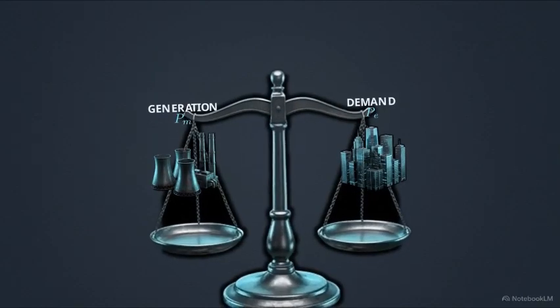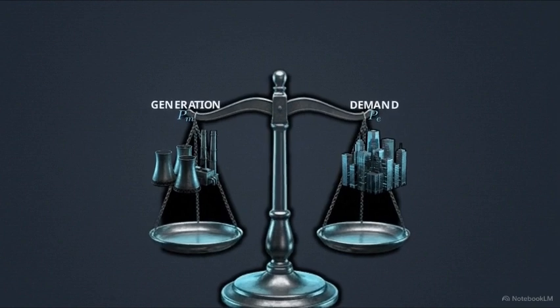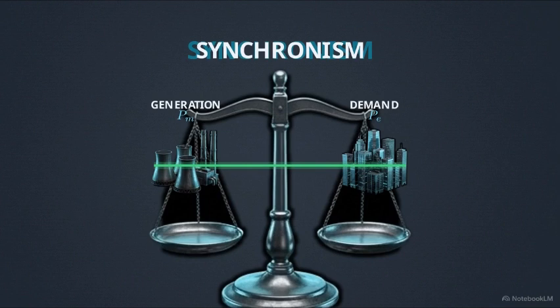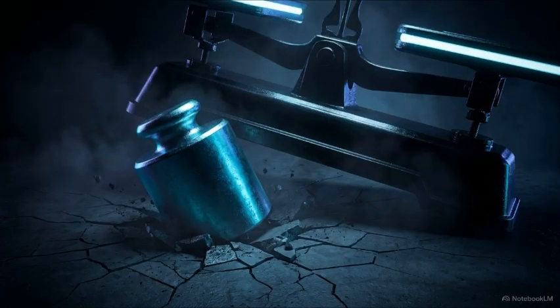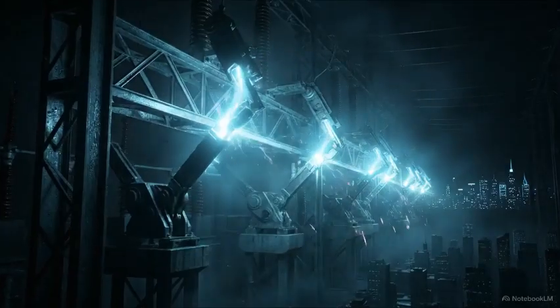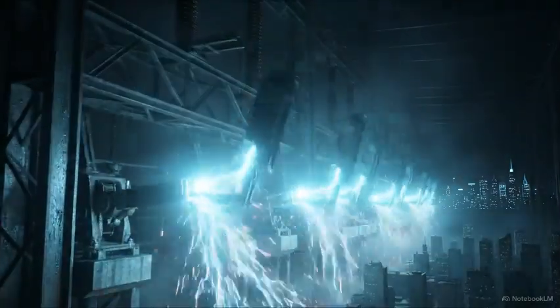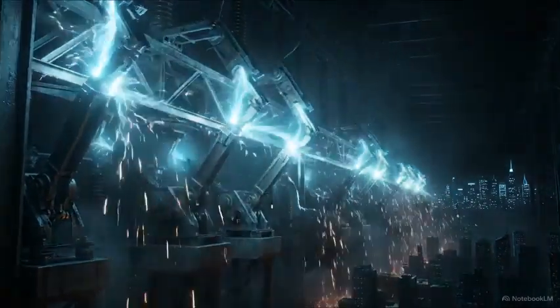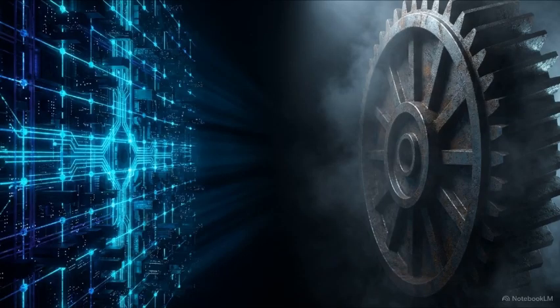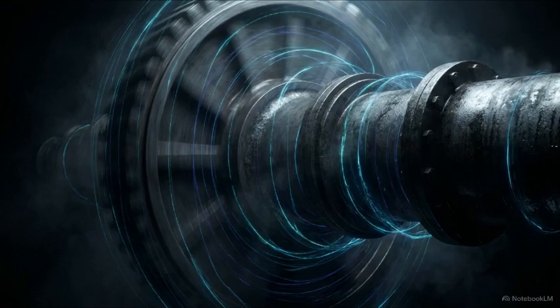This diagram represents a concept called synchronism. It shows the perfect, rigid balance required between the mechanical power entering the grid from power plants and the electrical power drawn out by consumers. If generators produce even slightly more or less than the exact demand, that scale tips. Frequencies drift, voltages collapse, and within seconds, protective relays will sever connections to save the equipment, triggering a cascading blackout. Keeping the lights on means waging a continuous, invisible war, pitting the raw physical momentum of spinning turbines against the electromagnetic resistance of the grid itself.